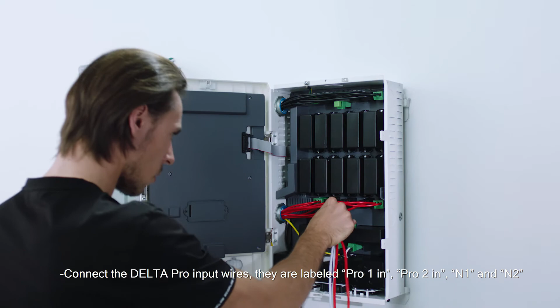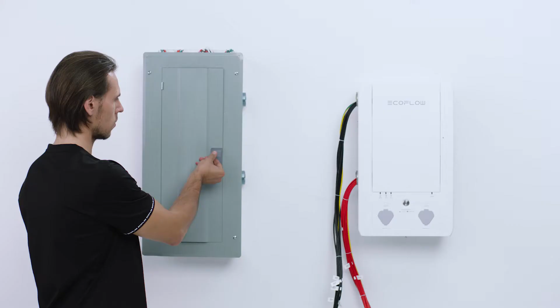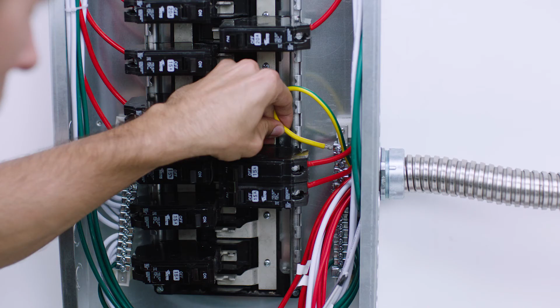Connect the Delta Pro input wires. They are labeled Pro 1 in, Pro 2 in, N1 and N2. Turn off the main breaker and each branch circuit breaker and make sure the system is completely de-energized using a voltage detector. Pass all of the wires through the conduits. Connect the ground wire and the two neutral wires to their buses.